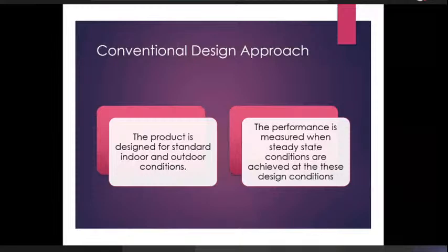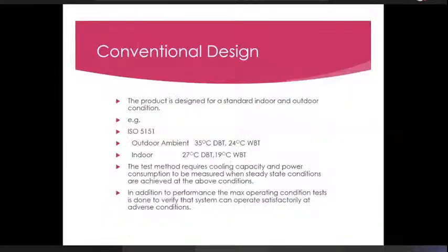So here is a little more formal description. The product in a conventional design is meant for a standard indoor and outdoor condition. So for example, if you look at ISO 5151, the outdoor ambient temperature is 35 degrees centigrade dry bulb temperature and 24 degrees centigrade wet bulb temperature. And the indoor conditions are 27 degrees centigrade dry bulb and 19 degrees centigrade wet bulb temperature.